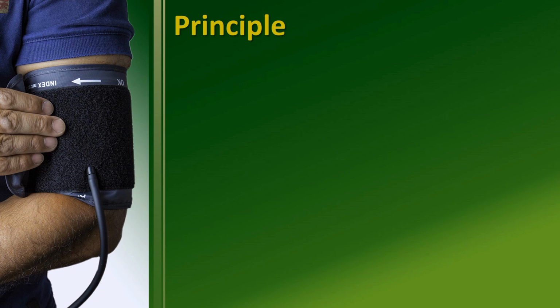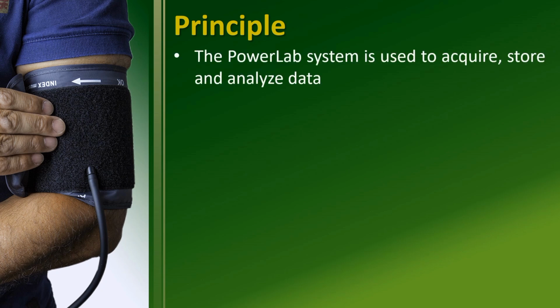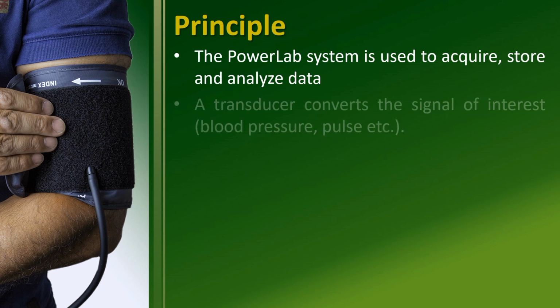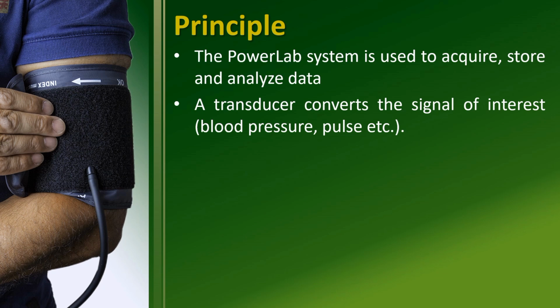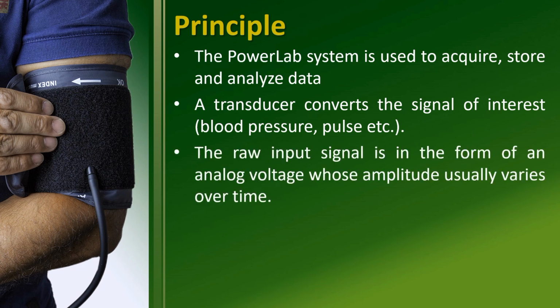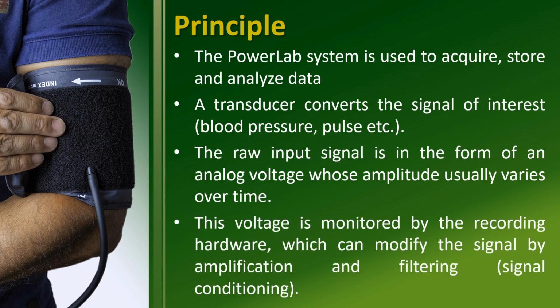The PowerLab system is used to acquire, store, and analyze data where a transducer converts the signal of interest, which can be blood pressure, pulse, or any other signal. The raw input signal is in the form of an analog voltage whose amplitude usually varies over time. This voltage is monitored by the recording hardware, which can modify the signal by amplification and filtering. This process is known as signal conditioning.